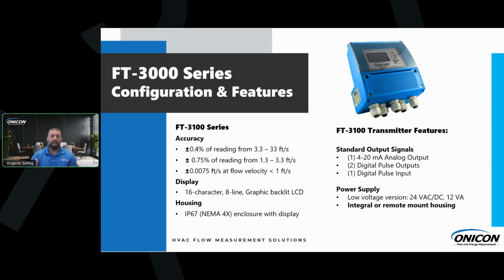So looking at the FT3100 series, this is our basic standard transmitter, plus or minus 0.4% of reading accuracy, up to 33 feet per second, just like the 32, but it starts at 3.3 feet per second, all the way up to 33 feet per second. There are no optional outputs with this. It is what it is. It's a low voltage only version. This can be remote mounted, but this being a less powerful transmitter, we can only go up to runs of 100 feet away from the flow meter body. After that, we could also add the amplifier to this as well.